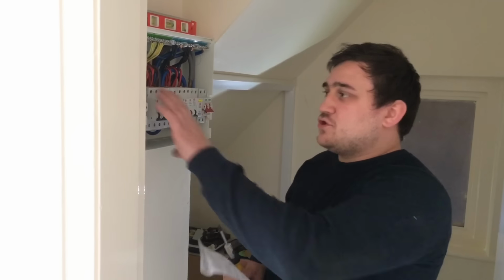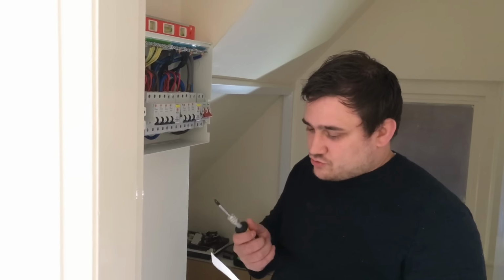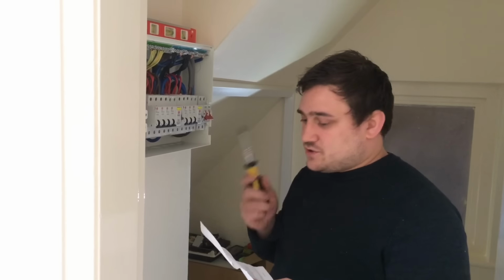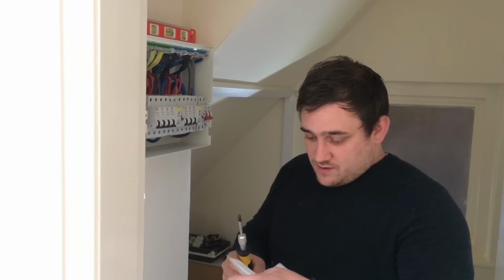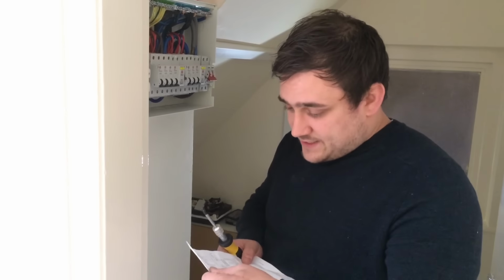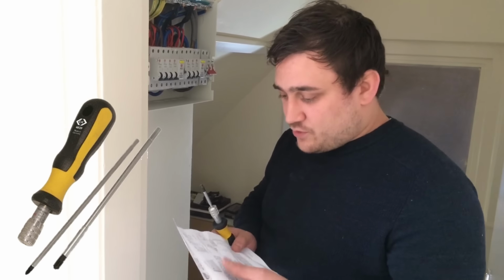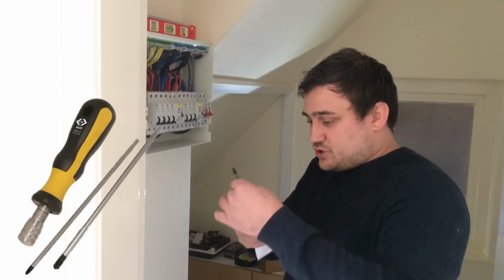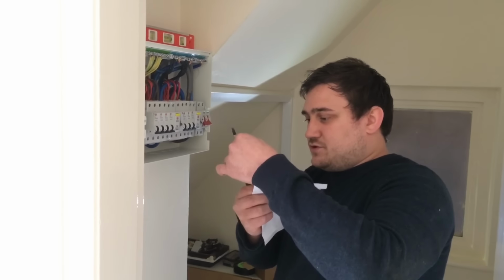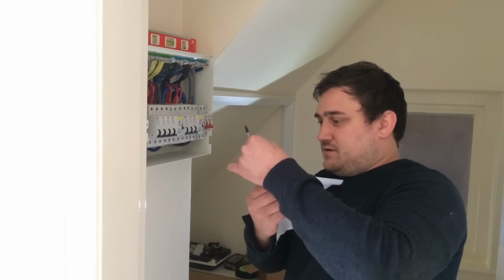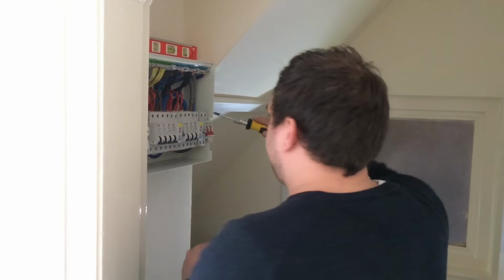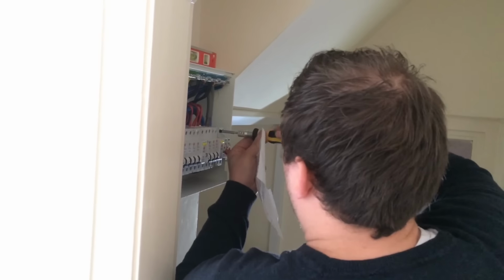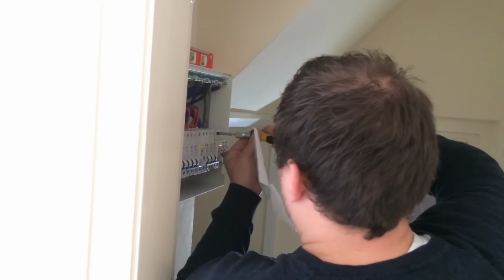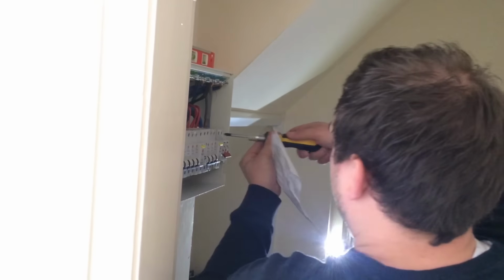All the breakers up. I've torqued the breakers to the correct settings with my torque screwdriver. I'm now going to do the main switch, so I'm just going to check on my paperwork to see what torque setting it should be. On here it says it should be 2.3 Newton meters, so I'm just going to adjust my torque screwdriver to the correct setting. There it is. I'm going to torque it up, and when it's torqued you should hear it click when it's at the correct torque. There we go.